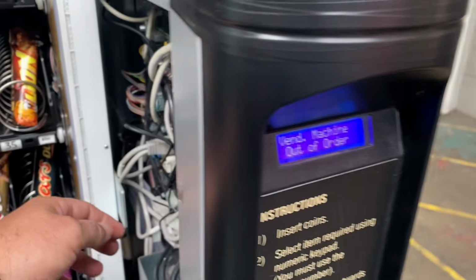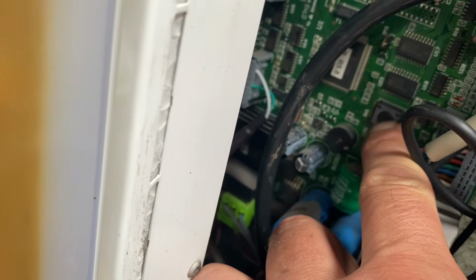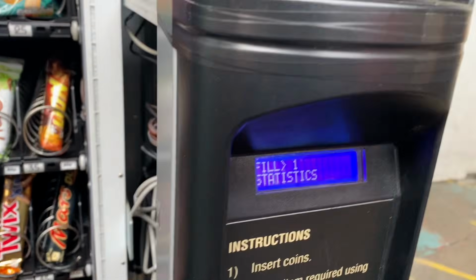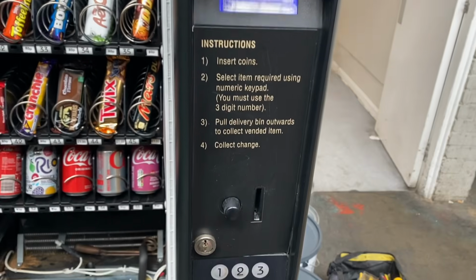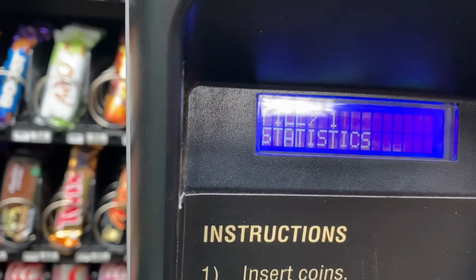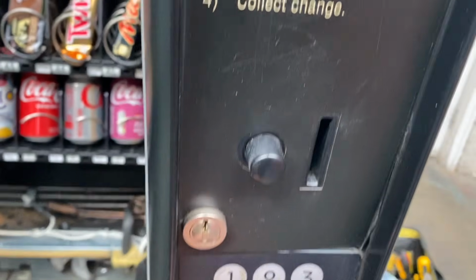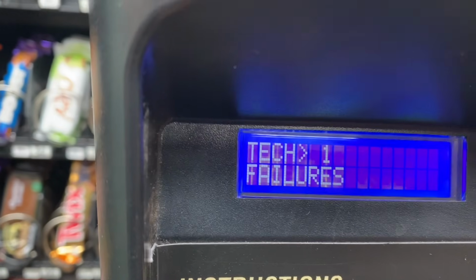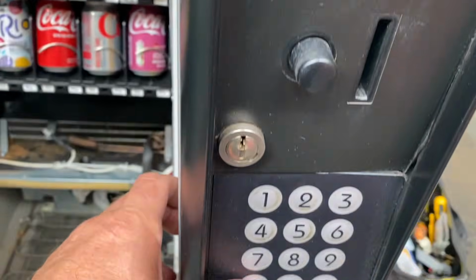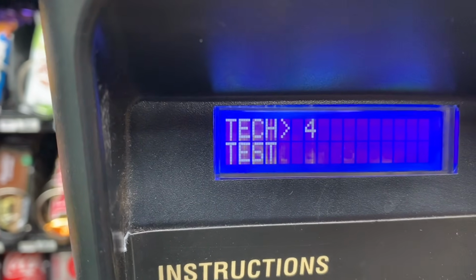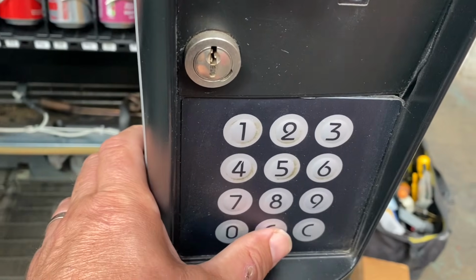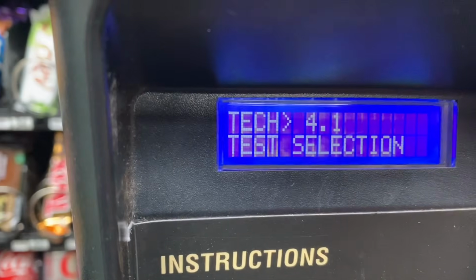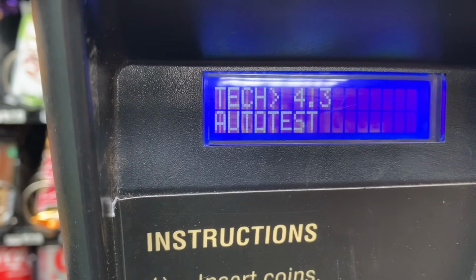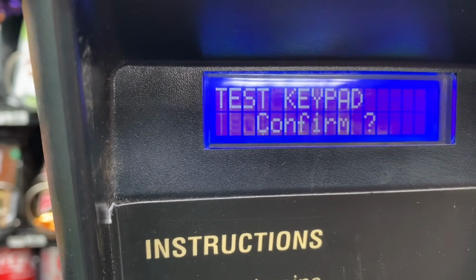And to double check that the fan motor isn't working, if you go into the menu button, press C, which should take you to the tech menu. And then if you press 0 and scroll through till you get to tech for test, press E to enter into test mode. Now you want to press 0 twice until you get to auto test and then press enter.